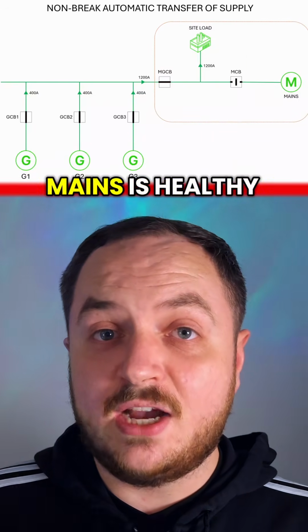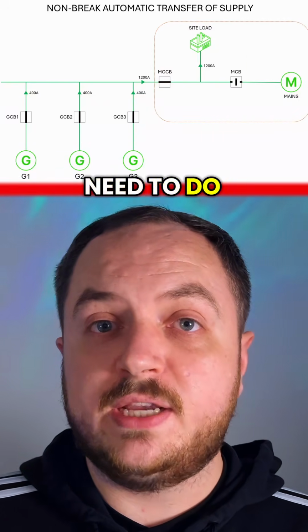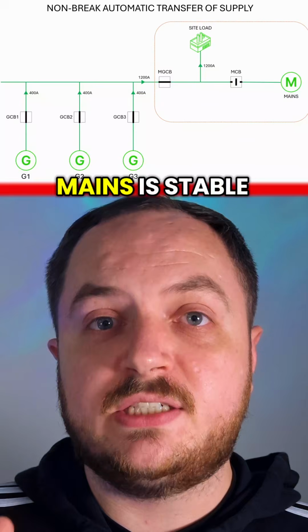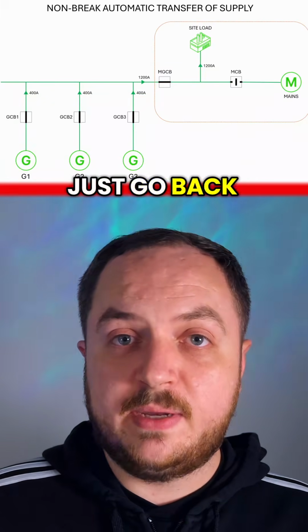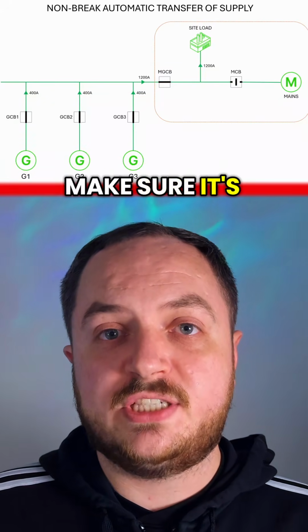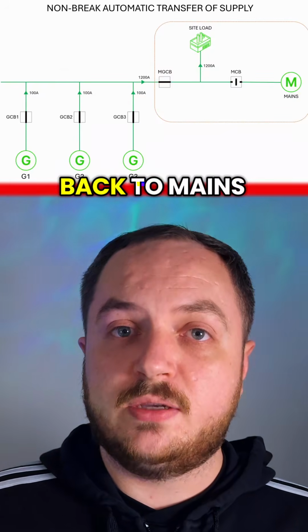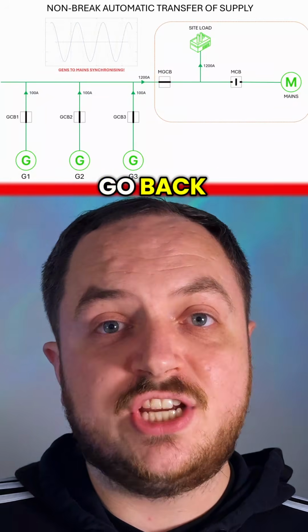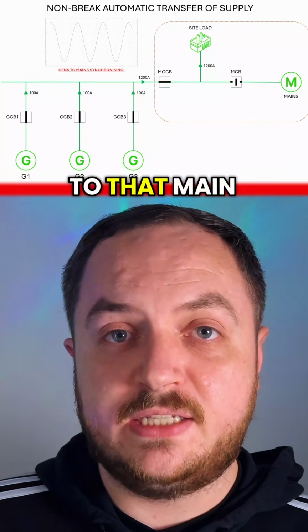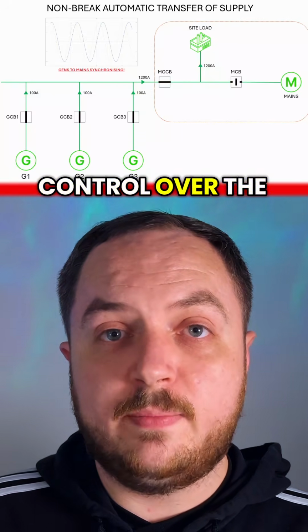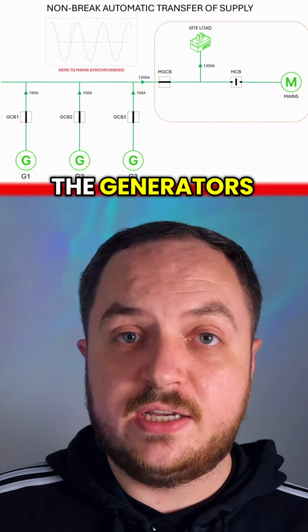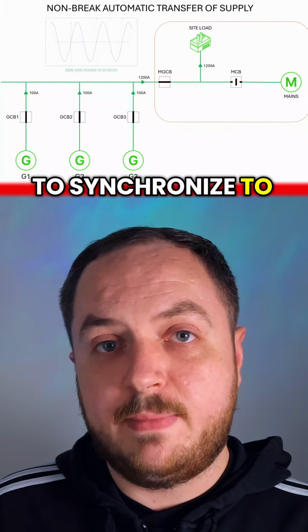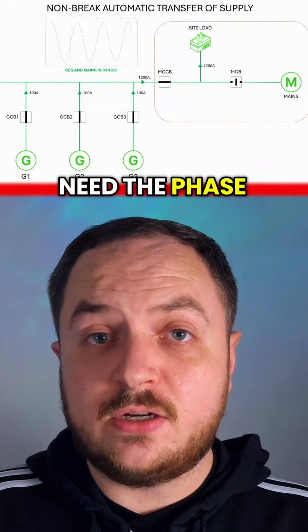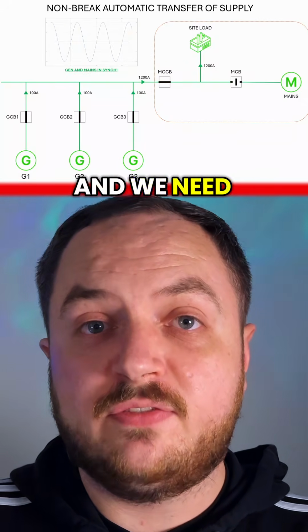Okay, so now the mains is healthy again. Now what we need to do is wait for a period of time that the mains is stable. We don't want to just go back to mains for it to fail again. We need to make sure it's stable and solid before we go back to mains. Okay, so when we're ready to go back, the generators need to synchronize back to that main supply. We have no control over the mains, so the mains can't synchronize to the generators; the generators have to synchronize to the mains. To synchronize, we need the phase angle correct, we need the voltage correct, and we need the frequency correct.